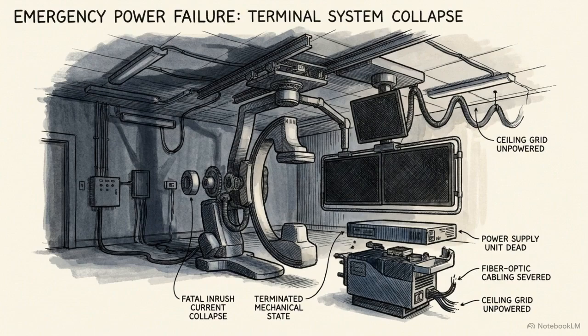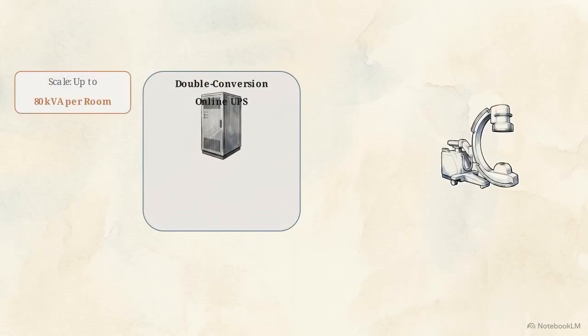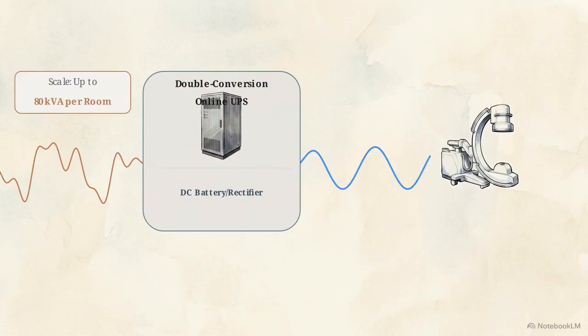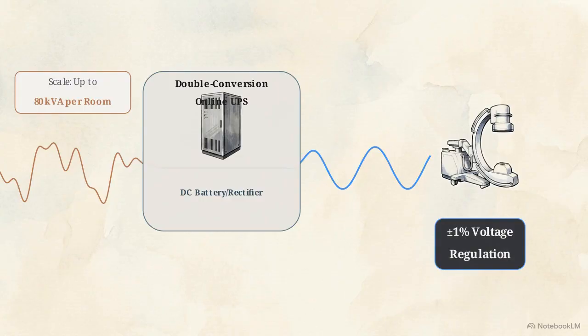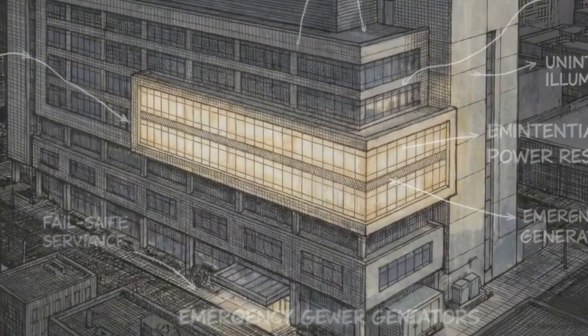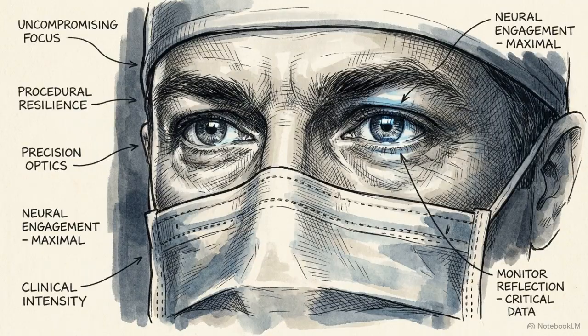Older fluoro-only uninterruptible power supplies simply collapse under this extreme inrush current, terminating the procedure instantly. The modern solution is a double conversion online UPS, scaled to provide up to 80 kVA per room. This double conversion isolates the gantry from the utility grid, converting AC to DC and back again. This filters all electrical anomalies and guarantees flawless 1% voltage regulation. During a blackout, the UPS acts as the final failsafe. It absorbs the massive imaging load instantly, holding the system stable until generators spin up. This uncompromising power topology ensures that procedural failure due to electrical artifacting or sudden blackouts is entirely eliminated from the equation.